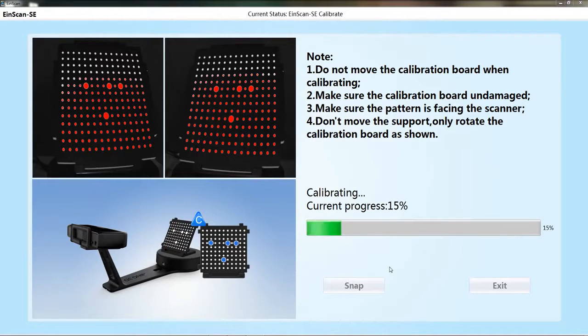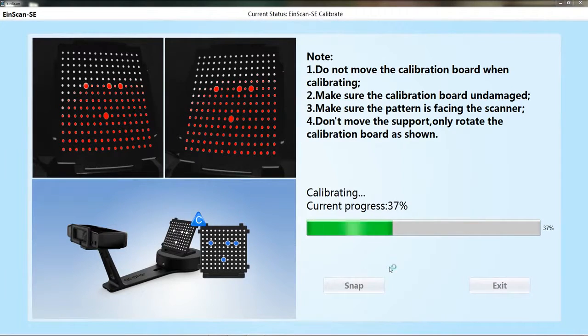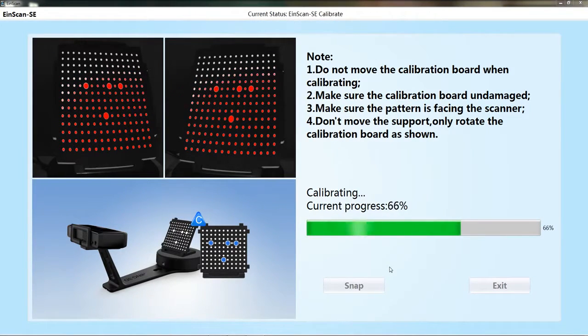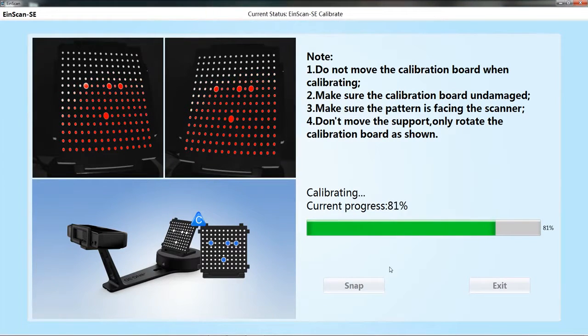After the collections for the three positions are completed, the software will calculate. Then the calibration interface will be automatically closed.